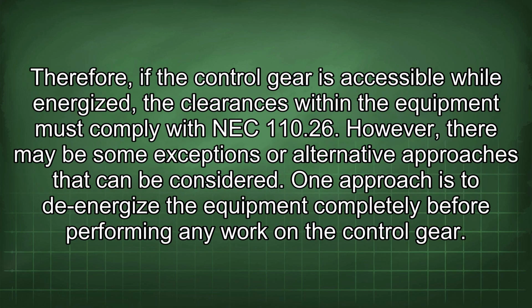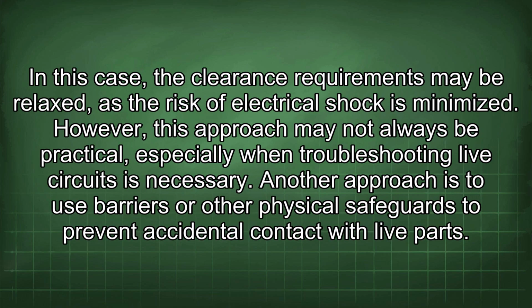Therefore, if the control gear is accessible while energized, the clearances within the equipment must comply with NEC 110.26. However, there may be some exceptions or alternative approaches that can be considered. One approach is to de-energize the equipment completely before performing any work on the control gear. In this case, the clearance requirements may be relaxed, as the risk of electrical shock is minimized. However, this approach may not always be practical, especially when troubleshooting live circuits is necessary.